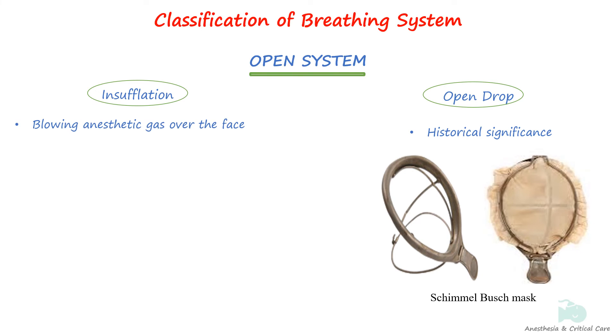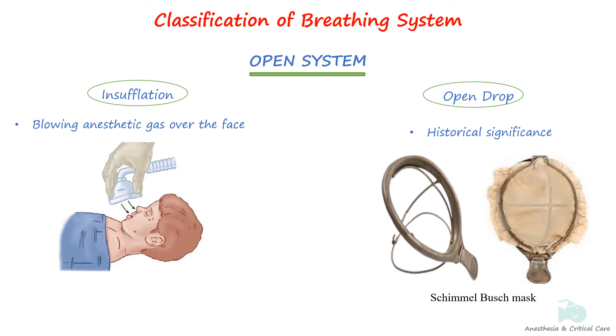Insufflation breathing is a technique used to blow anesthetic gases through a mask across a patient's face without the mask being in direct contact with the patient. This breathing system is most commonly used with pediatric patients when placing a face mask directly on the child's face may be difficult or resisted. Especially if the gas flow is high enough, there is virtually no re-breathing of exhaled gases.